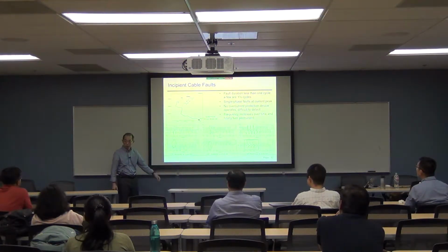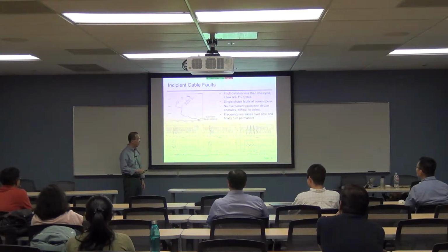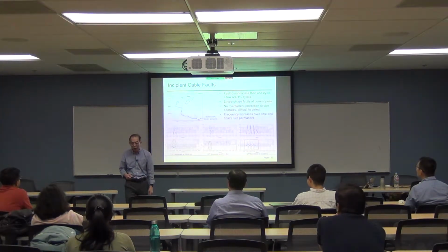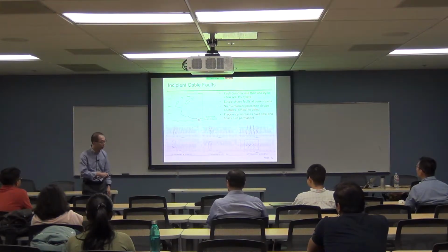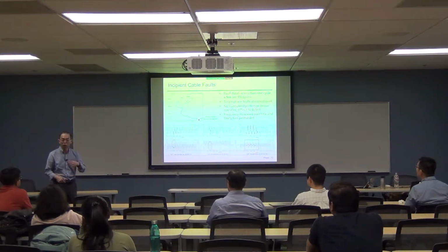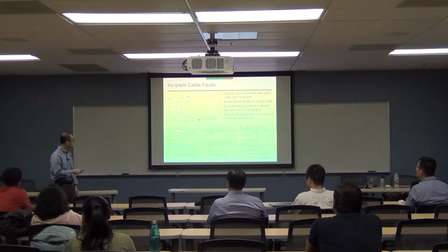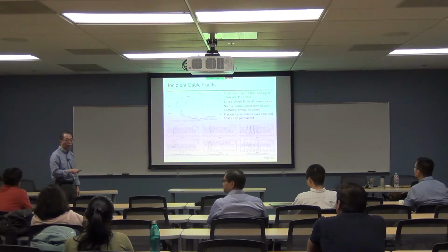And then it disappears, okay? And then the protective relay upstream will not typically see this type of fault because it self-clears so fast. The only thing that it sees is the voltage waveshape fault in here, okay?